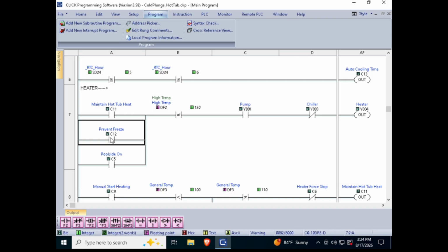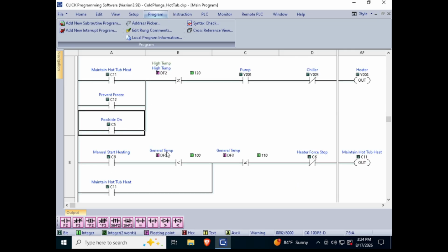In other words, if the water goes below 40-some degrees, this will automatically kick on. But there are certain conditions that have to be true for the heater to be on: the chiller cannot be on, the pump has to be on, and the temp cannot be 120 or over. So that's basically why you can just keep adding different sub-processes here.